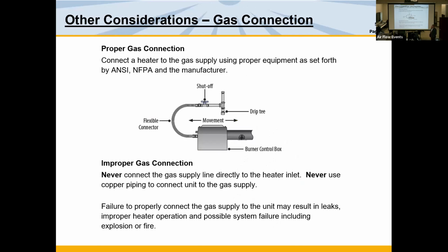The requirements now for installing an infrared tube heater are that we, the manufacturer, must provide a flex hose, and the contractor must install it in a C configuration, just like that. There's no getting around it. I can't tell you how many times I see that not done right. Why the C configuration? Somebody want to guess? Expansion and contraction. Each cycle of an infrared heater on or off is 2 to 6 inches of movement. That configuration allows for the movement.